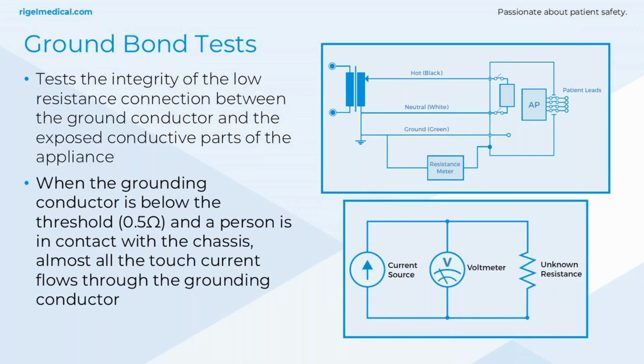There are a few diagrams for the resistance meter in NFPA 99, but this example shows how the 2-wire method works, and it's simple but effective. So the measured values of ground bond vary from standard to standard, but in NFPA 99 it's 500 milliohms or 0.5 ohms.